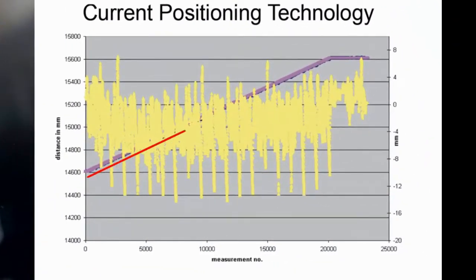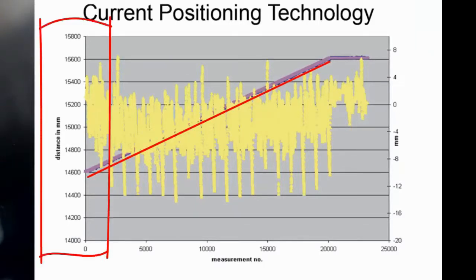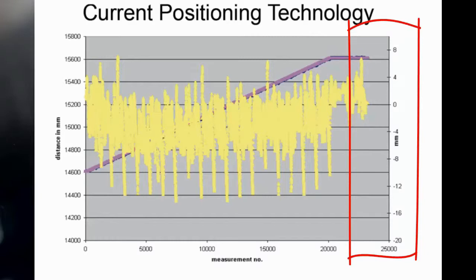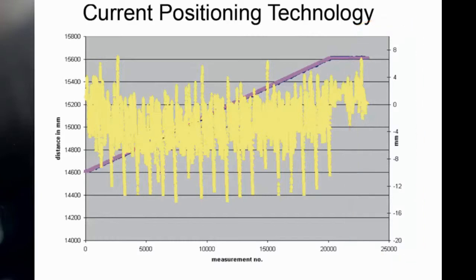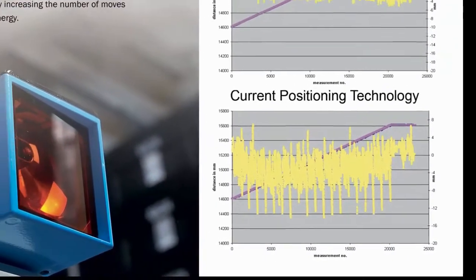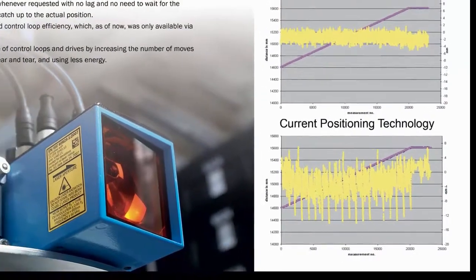The straight line in the graph shows a linear position of a vehicle and corresponds to the y-axis data on the left side. The yellow data shows the deviation between the measured and actual position, represented on the right side y-axis. This jitter is a common effect of the sensor output being asynchronous to the PLC position requests, causing wear and tear on the drive system, energy loss, and requiring less-than-efficient control loops and filtering to deal with its inherent position information error.